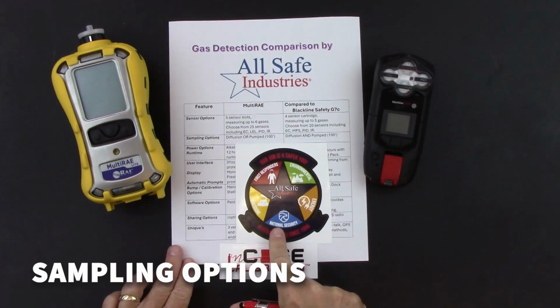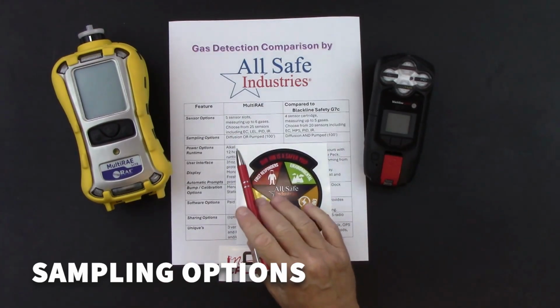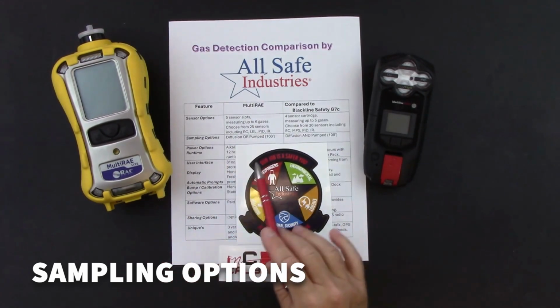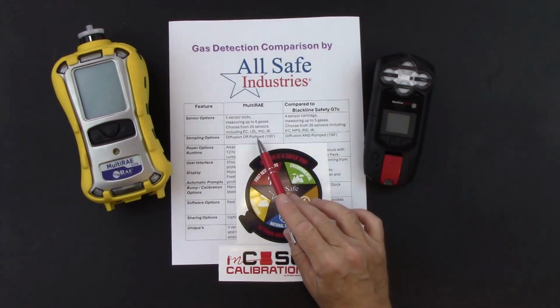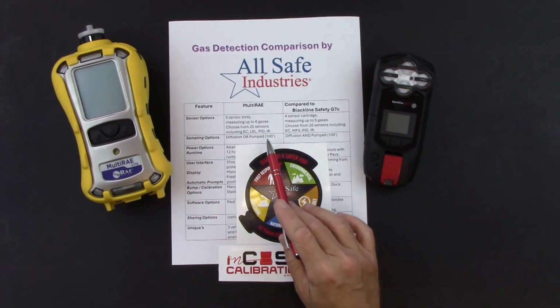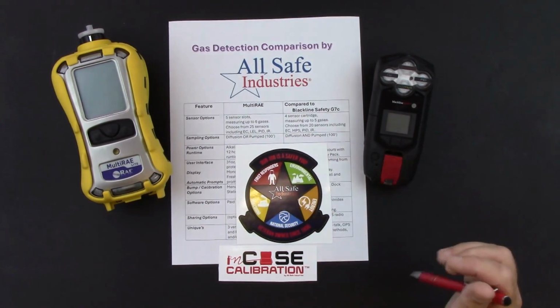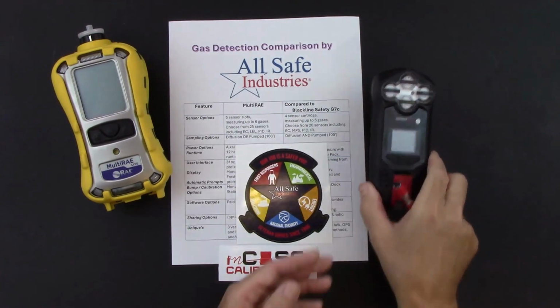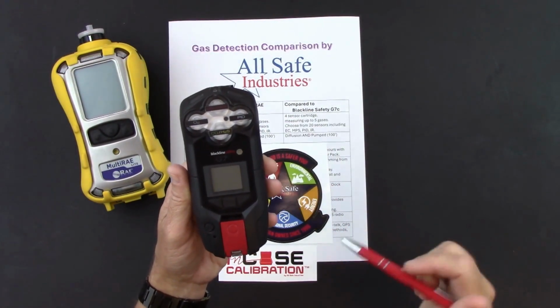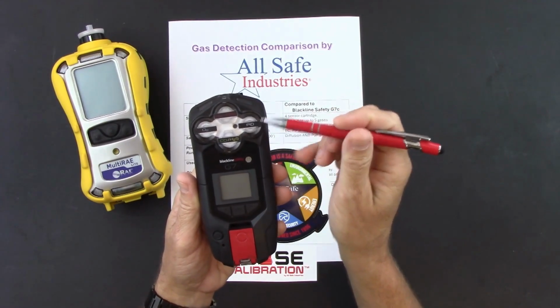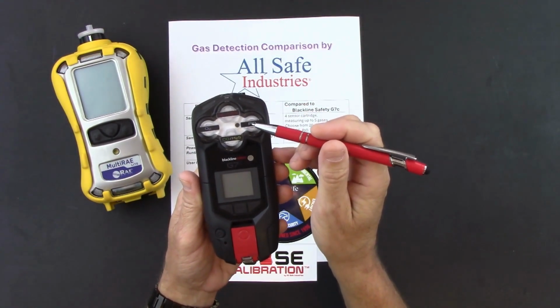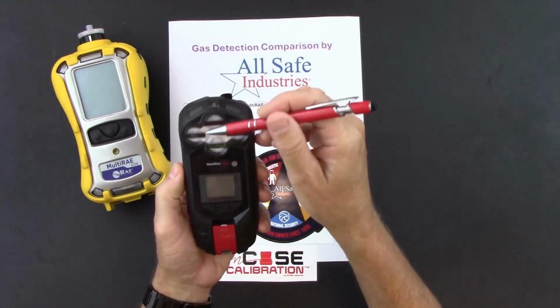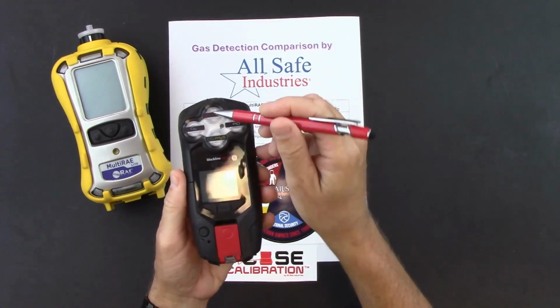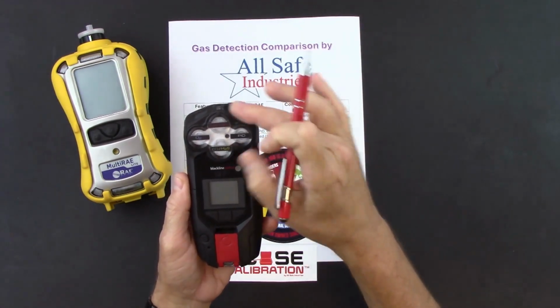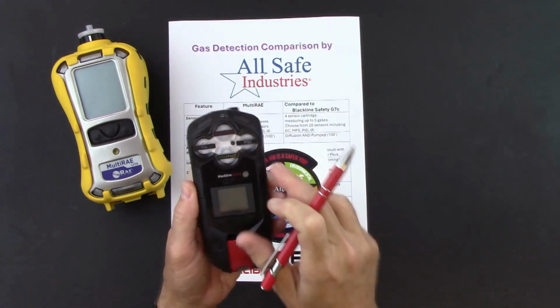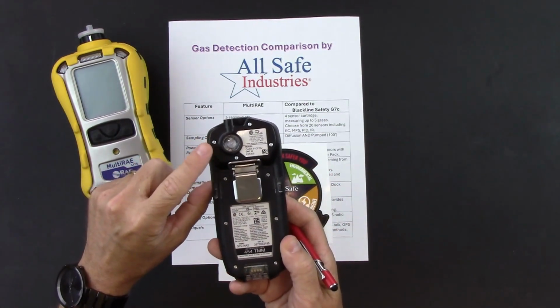For sampling options, the MultiRAE can either be a diffusion in the MultiRAE Lite, or all of the other versions of the MultiRAE would be a pumped instrument, pulling through up to 100 feet of tubing. The Blackline Safety G7c is diffusion and pumped. So if I was using this in diffusion mode, and that's how a G7c boots up, is in diffusion, you can see some gaps underneath these little label bars, and that's how the gas diffuses into the sensors in diffusion mode. But this unit also has a pump module on back.